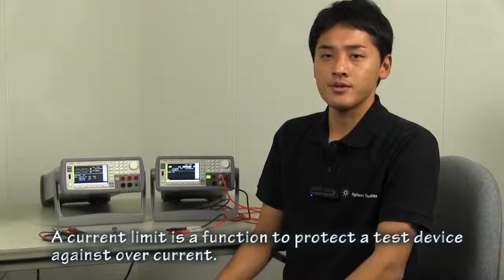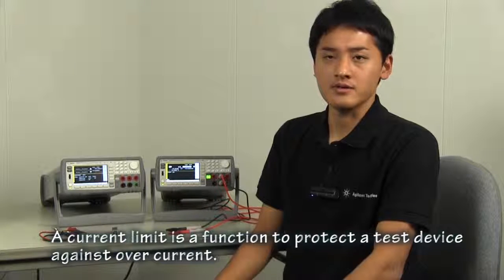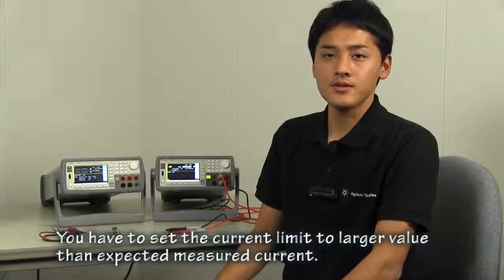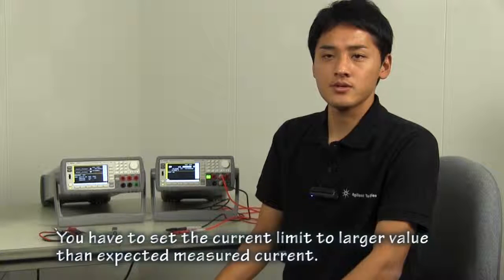In addition, you have to care about current limit to use the SMU as an ammeter. A current limit is a function to protect a test device against overcurrent. In this case, you have to set a larger value than expected measured value.